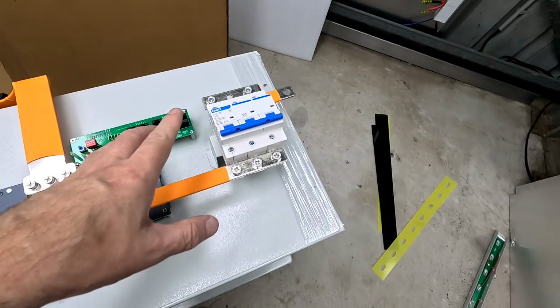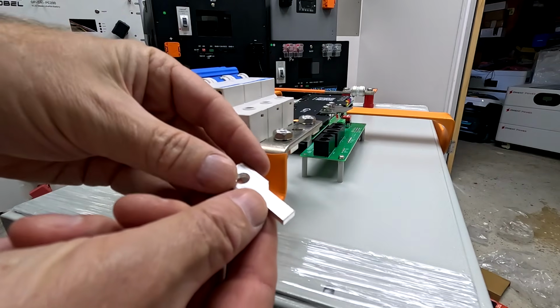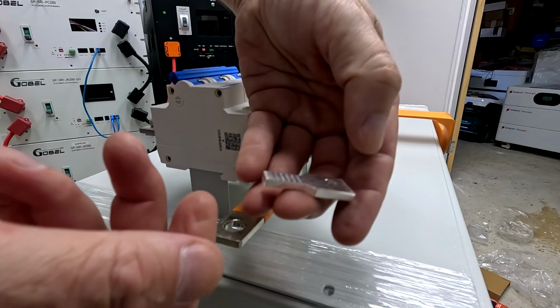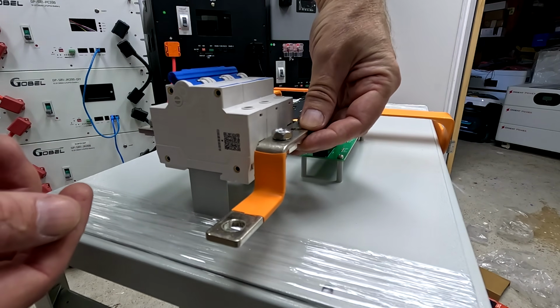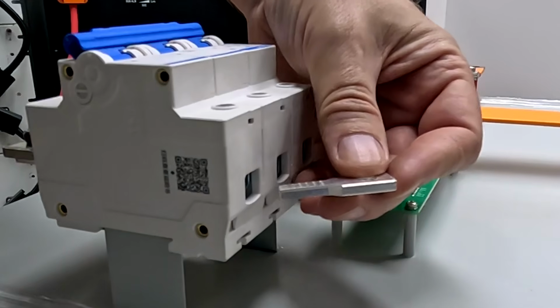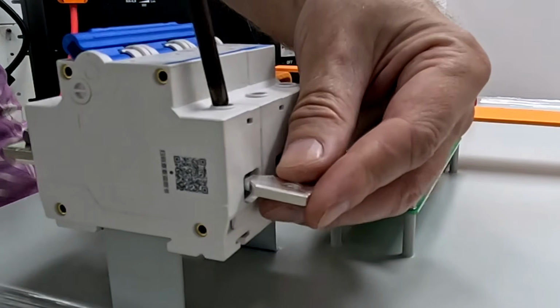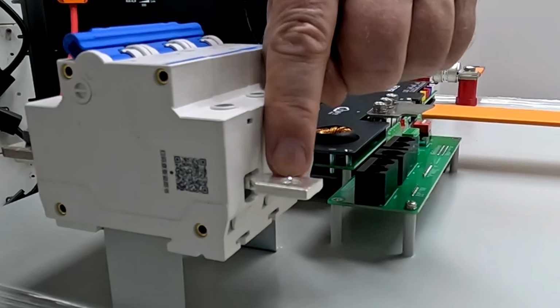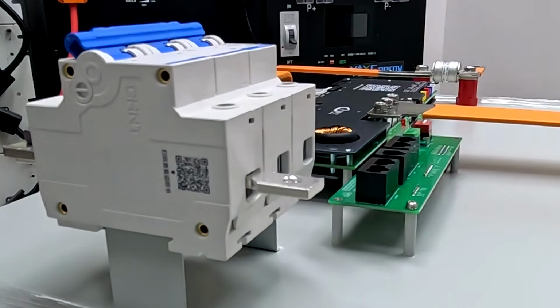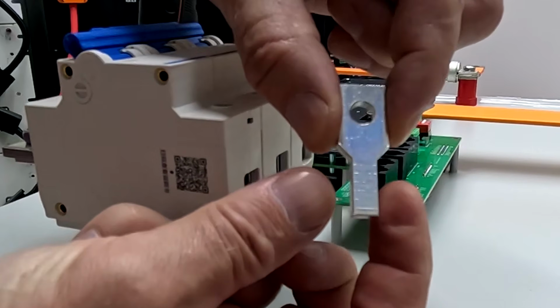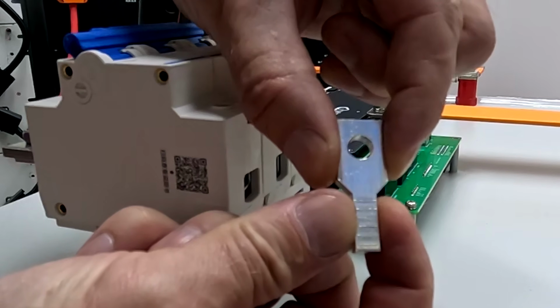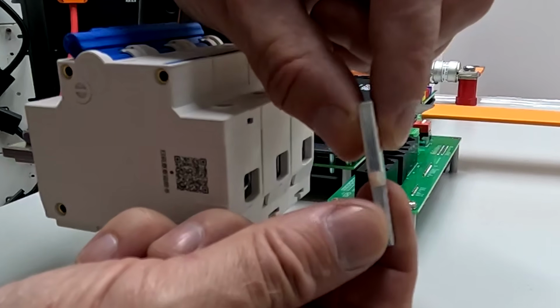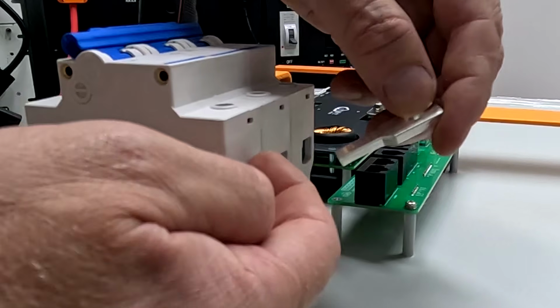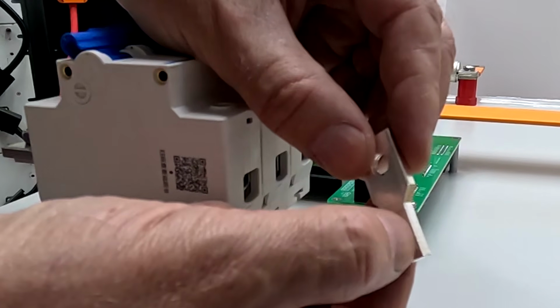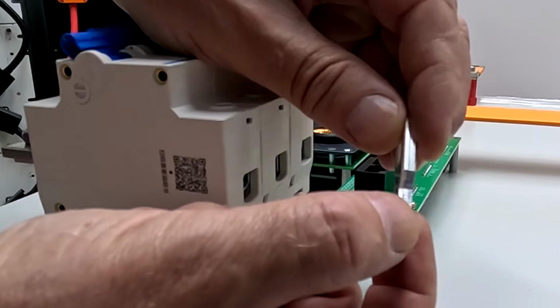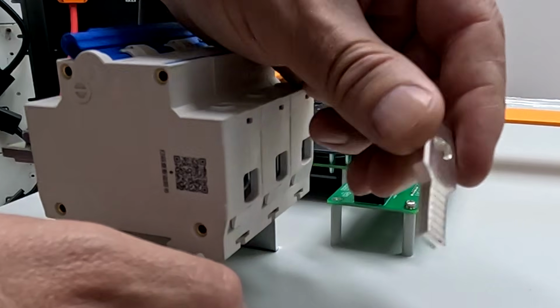So the breaker, I have to show you this. This is basically a copper link which connects the breaker to the bus bar. Let me take this one off - the link goes in here, then you tighten the screw, and you've got your M8 thread on the other side to connect to the bus bar. We've got this width on this side, and it halves on the other side where it sticks into the breaker, but the thickness doesn't change. So you're taking half the material away going into the breaker. I would have expected this side to get double as thick to compensate for the loss in width, but no, it's not.